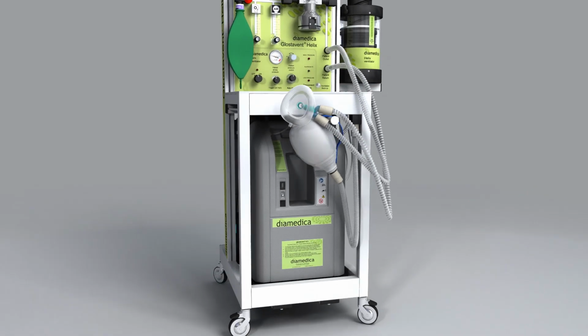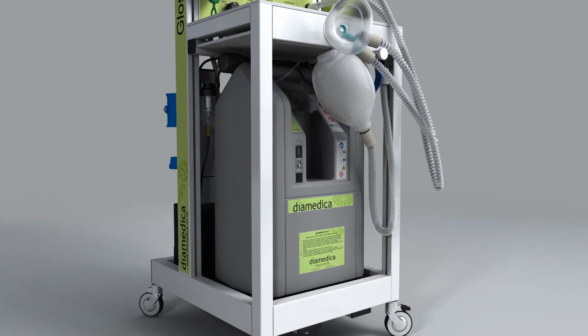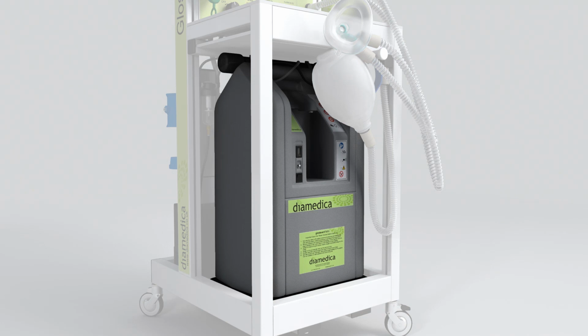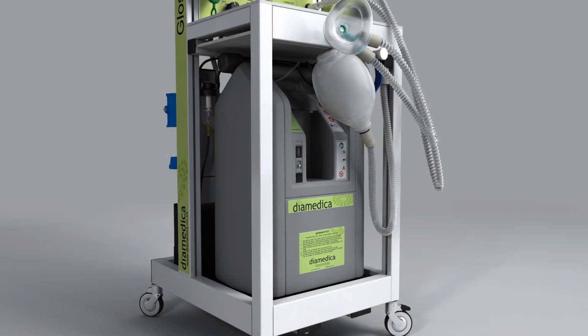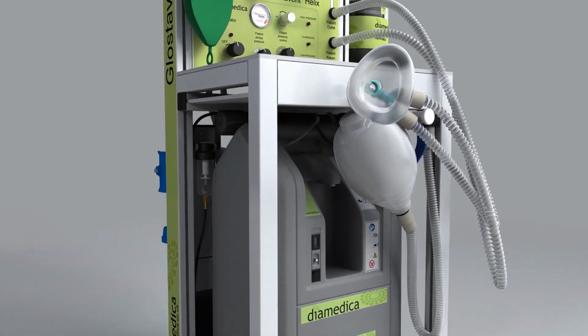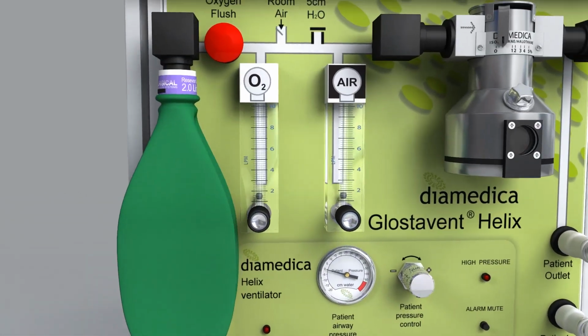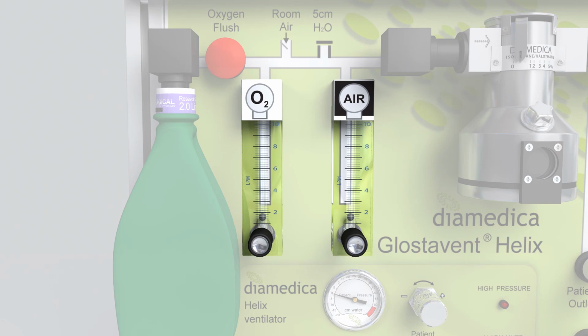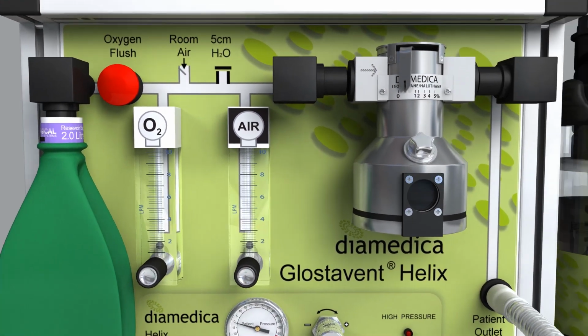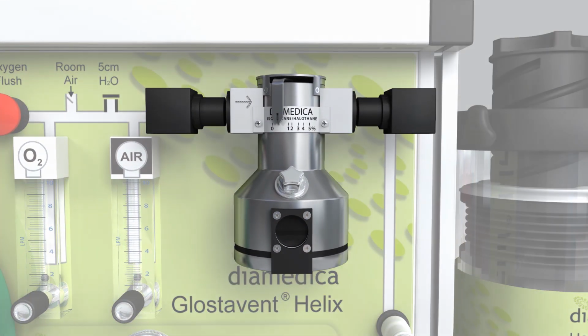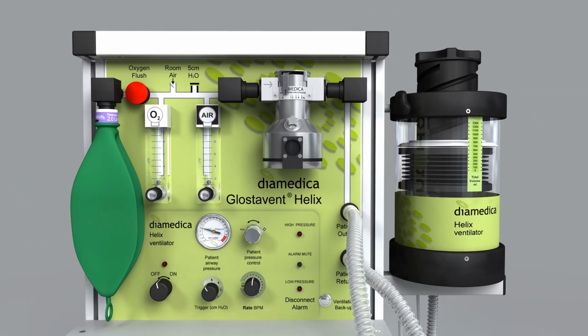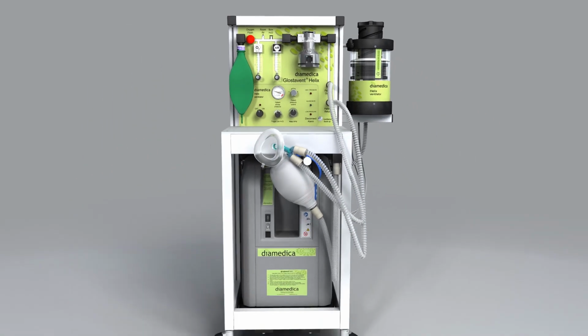The machine has an integral oxygen concentrator which produces medical oxygen and air. It has been designed to run if the power is intermittent or non-existent. It has 2 flow meters controlling the supply of oxygen and air which flow into the back bar connected to the low-resistance draw-over vaporizer. The gases are drawn in by the ventilator over the vaporizer, where they pick up the anaesthetic agent and become the carrier gas. This is then delivered to the patient.